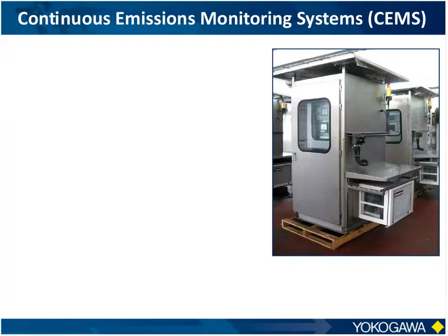Those ranges are also defined by government mandated requirements. The sample system design can be critical because these tend to be very hot, very wet samples, so you need to make sure condensation doesn't occur. But there are a lot of well-defined solutions, so it's usually not too bad, you just need to know the conditions to get the proper design.